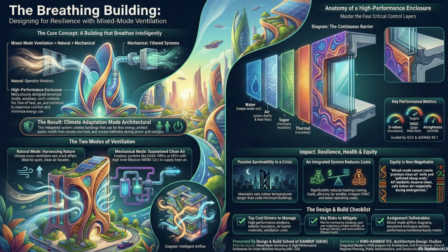Right. But more importantly, there are zonal strategies. So you might have a building where the units on the quiet courtyard side are designed to be in that green zone operation as much as possible, maximizing natural ventilation. But the street side is different. The units facing a busy, noisy street might be designated to be in mechanical mode 95% of the time, and that means you have to design that facade with enhanced acoustic attenuation just to make them habitable. So you're designing for different conditions on the same building. You are, and that requires some really complex control sequencing to manage it all.